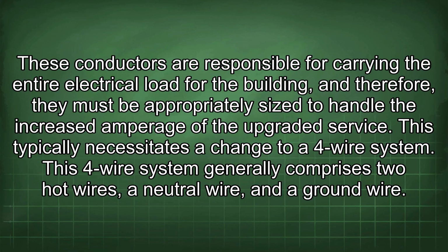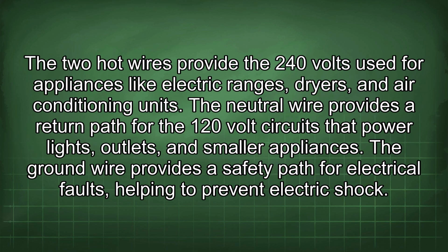This 4-wire system generally comprises 2 hot wires, a neutral wire, and a ground wire. The 2 hot wires provide the 240 volts used for appliances like electric ranges, dryers, and air conditioning units. The neutral wire provides a return path for the 120 volt circuits that power lights, outlets, and smaller appliances. The ground wire provides a safety path for electrical faults, helping to prevent electric shock.